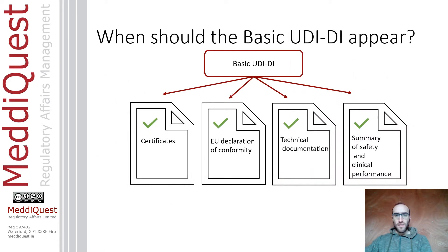The Basic UDI-DI is referenced in relevant documentation such as certificates including Certificate of Free Sale, EU Declaration of Conformity, technical documentation, and Summary of Safety and Clinical Performance.